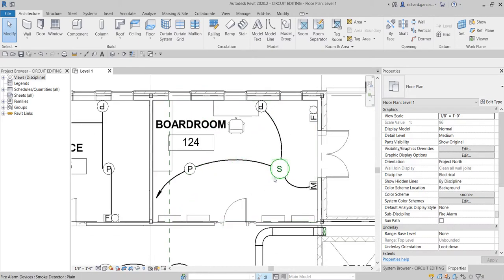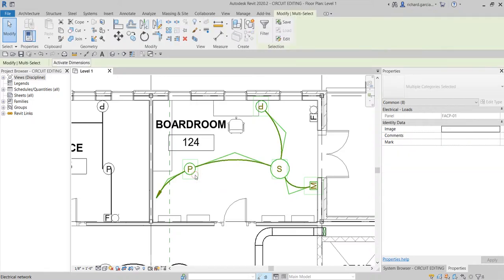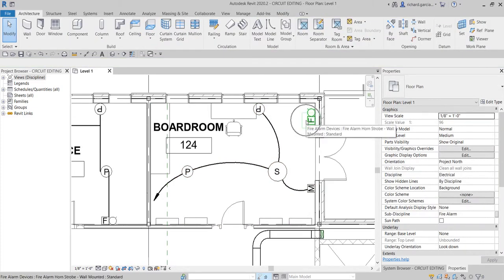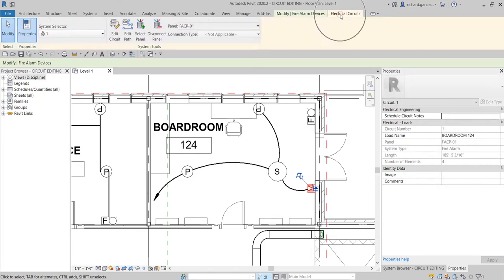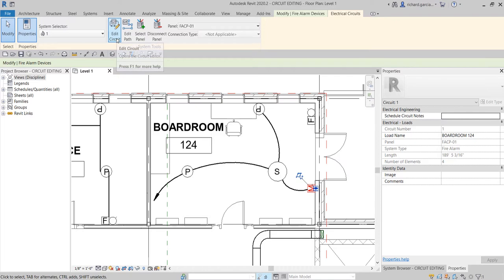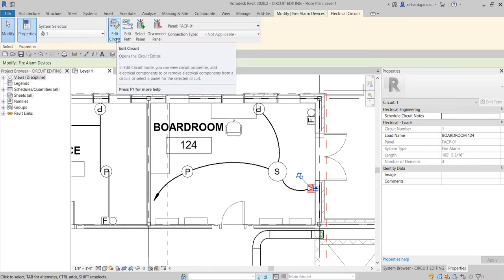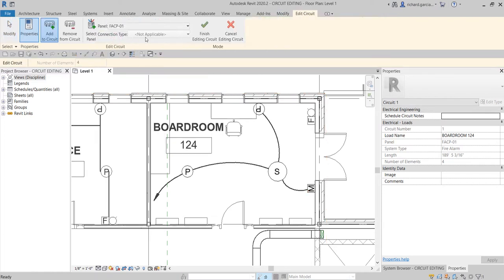I want this new device added to the existing circuit. Remember, if you hover your pointer over one of the devices and press Tab, then click, it will tell you which panel it belongs to. I want it connected to Fire Alarm Control Panel 01. To do that, select one of the existing fire alarm devices — you'll see a contextual tab called 'Electrical Circuits,' and within it, an 'Edit Circuit' option.